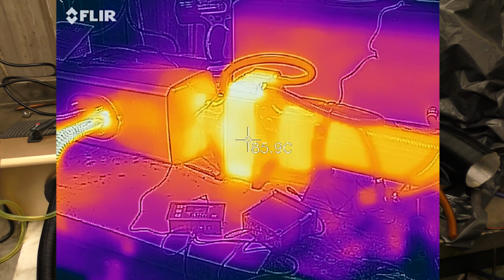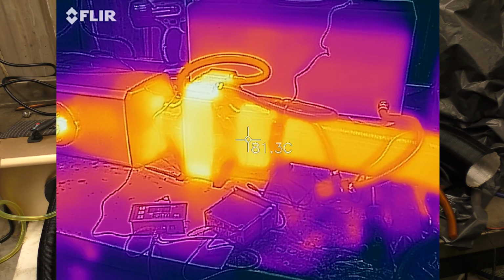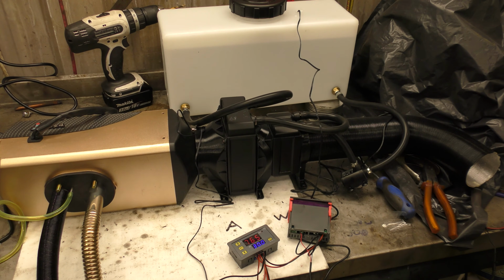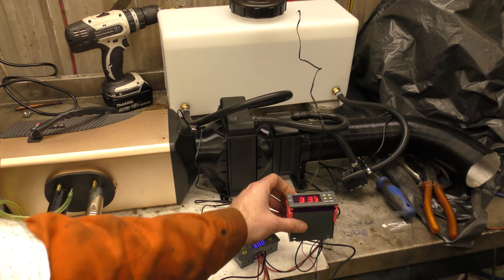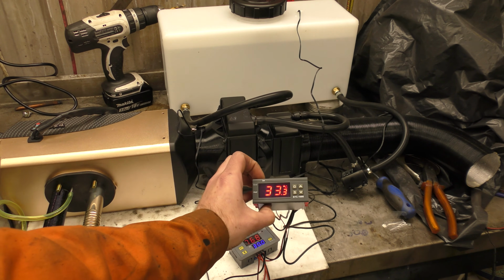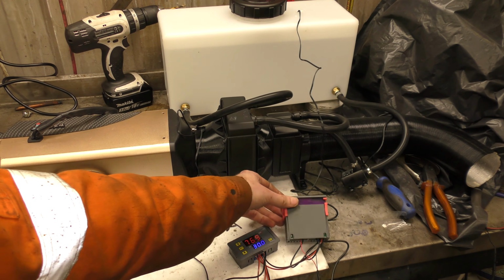Right, back over looking on the FLIR camera. The inlet and outlet are very similar. And what's the tank temperature? The tank should have probably stayed about - so the tank temperature's only gone up a degree and a bit, which is good, that's what we want to see.